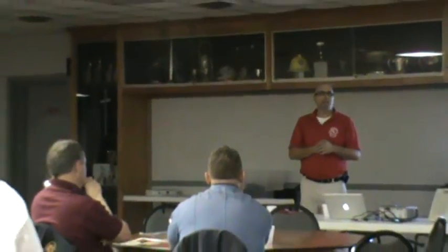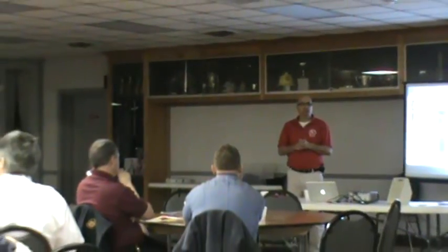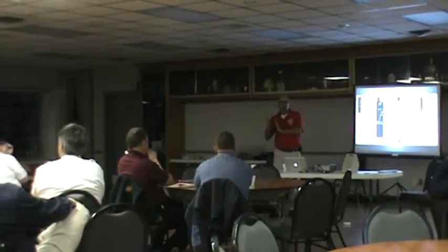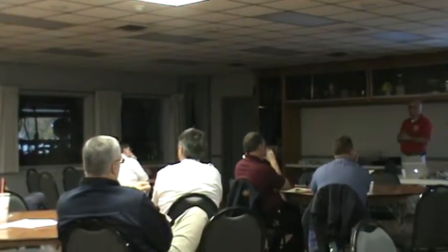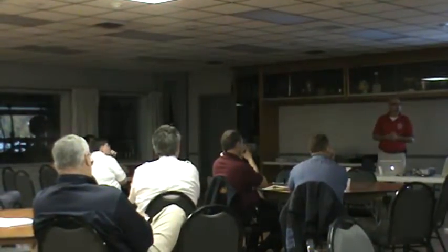Now, we've also said that in that 25-year period, this should not be considered a fire escape inspection. It should be a wall inspection of the wall that the fire escape is currently attached to. So in a 25-year cycle of inspection, it's a wall inspection for the whole entire wall of which the fire escape is currently a part, that's all. You know what I'm saying? So it's sort of a wall inspection that picks up the fire escape. Does that make sense to you guys on the 25-year rule? Because the 5-year inspection rule keeps picking up everything external to the wall. Okay? Any other questions on that?